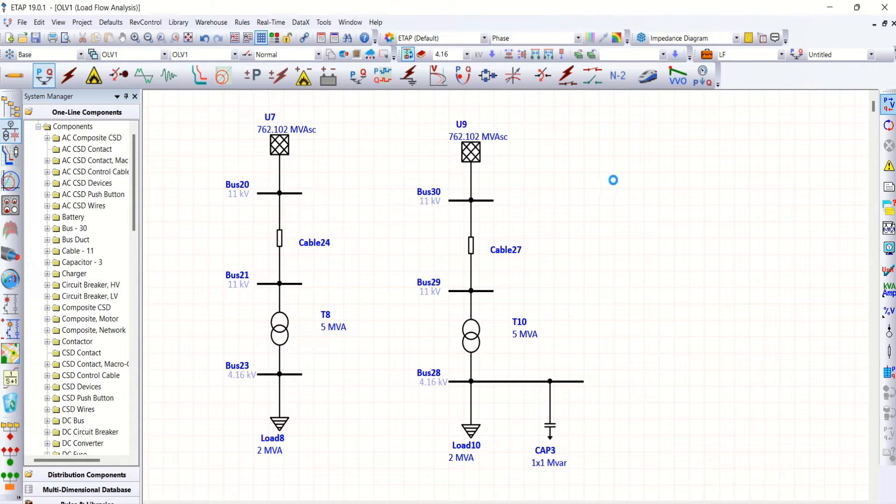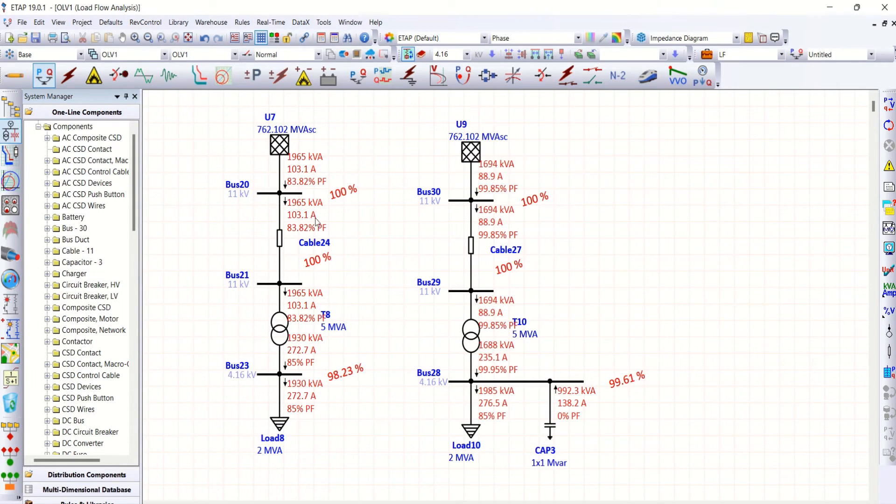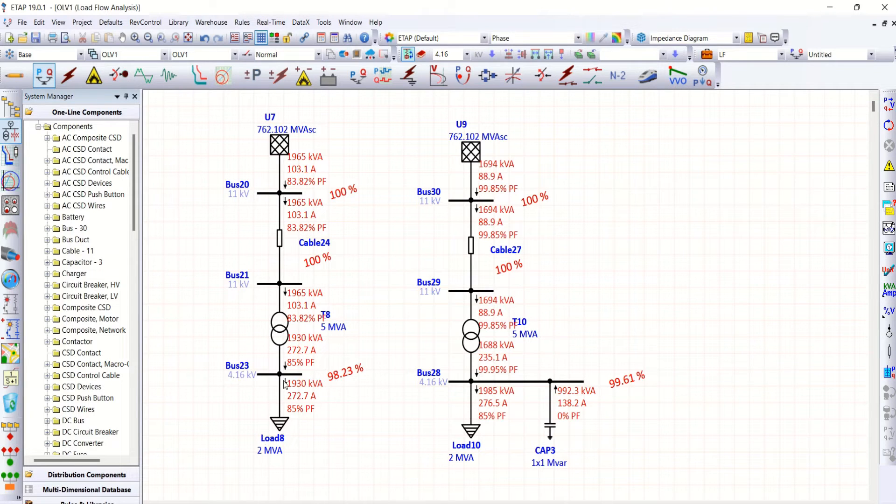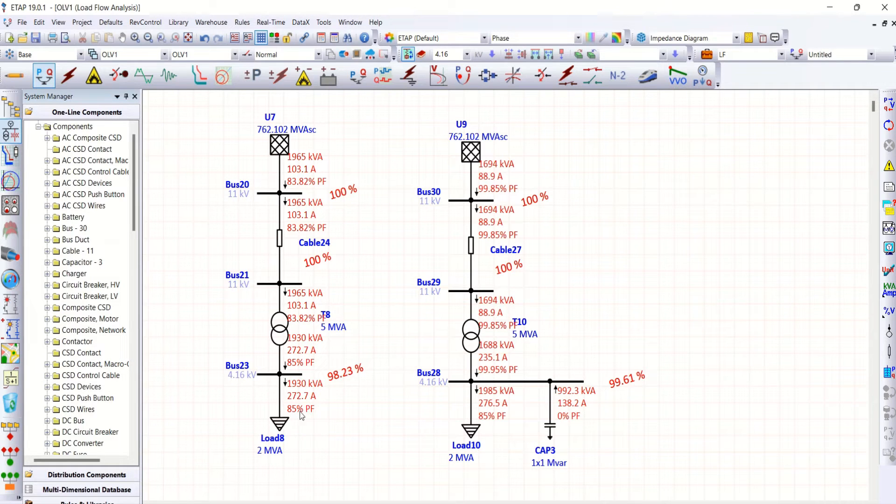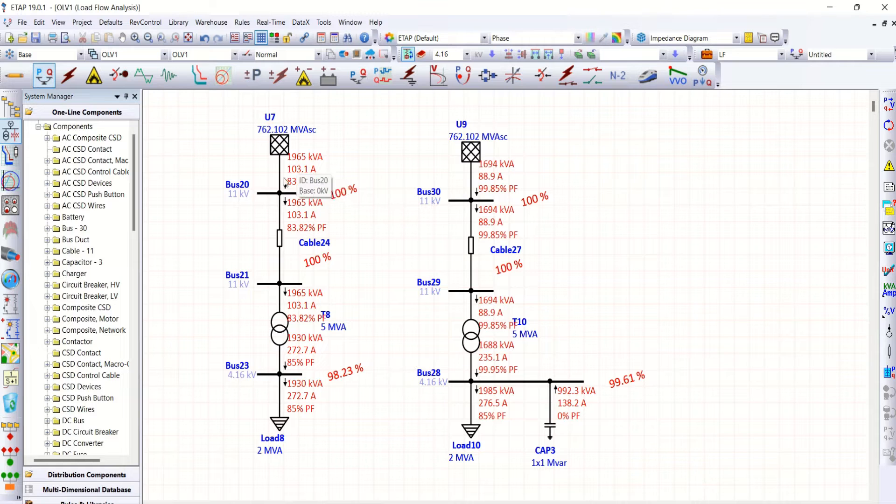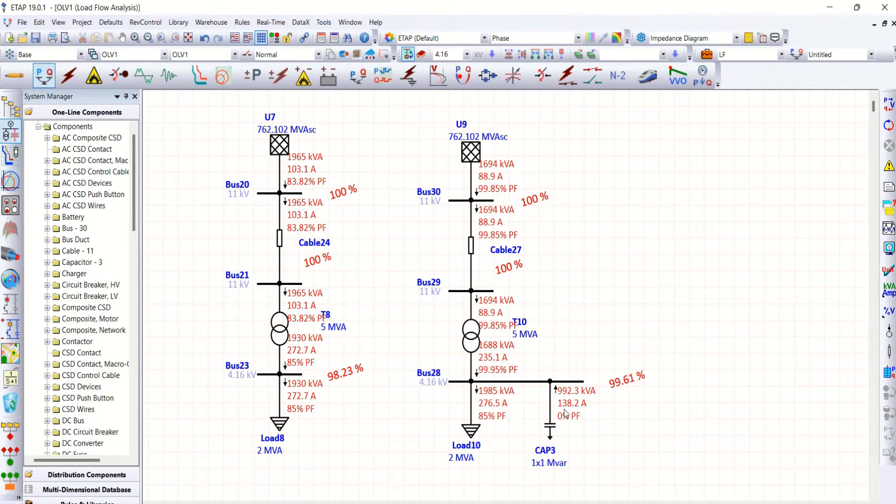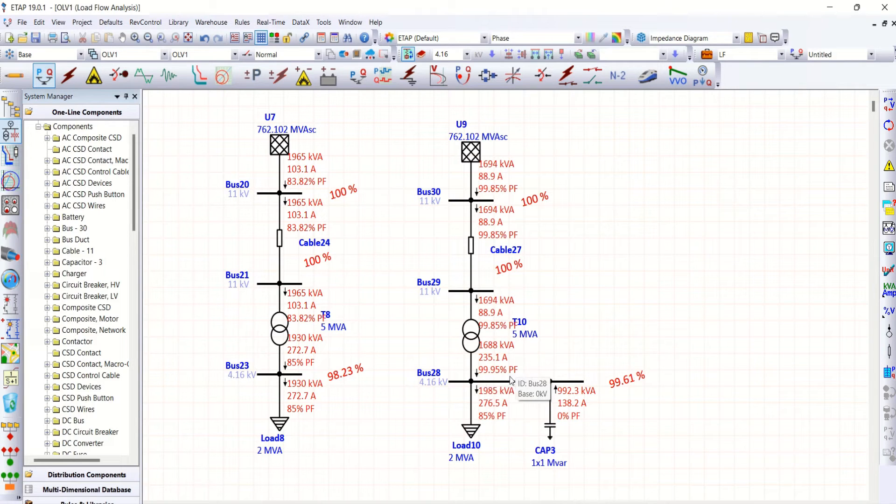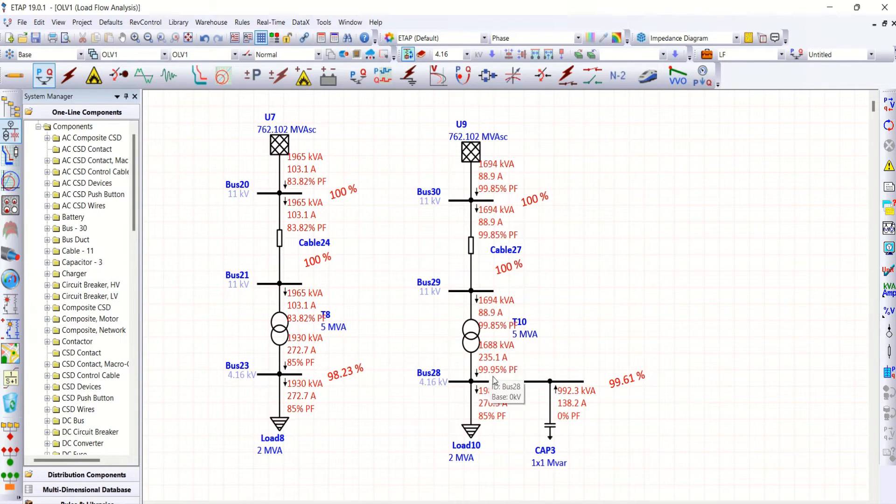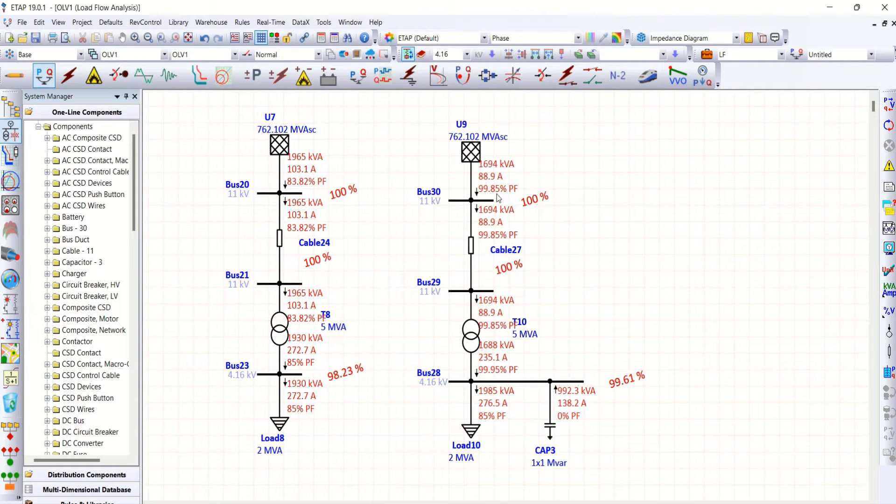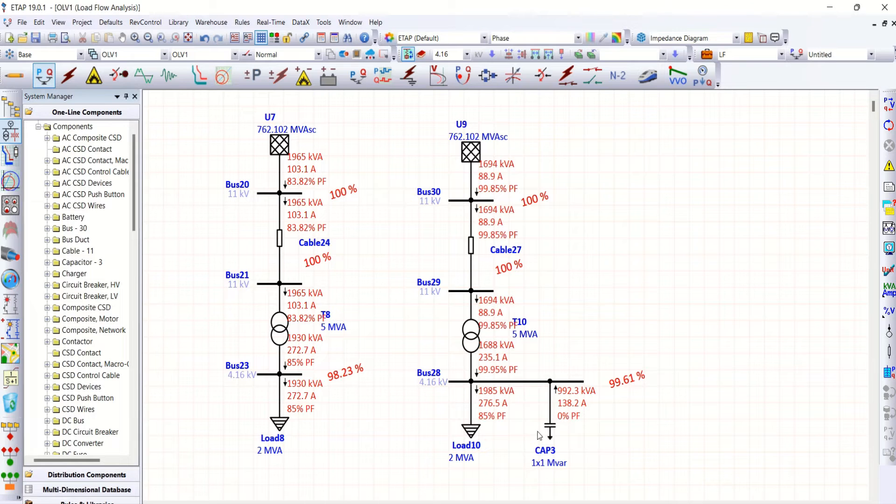Then you could see the difference between these two. Here, one without capacitor bank has 85% of power factor at load side and 83.82% of power factor at grid side. One with capacitor bank has 99.95% of power factor at load side and 99.85% of power factor at grid side. So addition of capacitor bank improves power factor. This is well known.